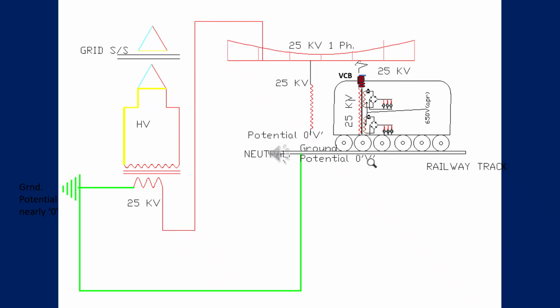That means if you turn on a switch, it will open the port of some valve with magnetic attraction to let air pressure enter, and this air pressure will close the contactor. This is electro-pneumatic. Then there is some electromagnetic, but in our OHE system we are mainly using electromagnetic. The pneumatic system is almost not used in our traction system.